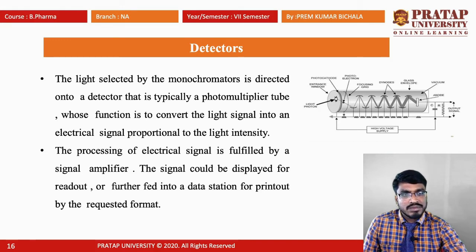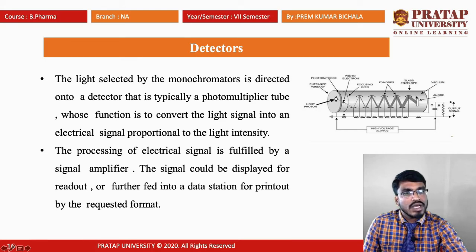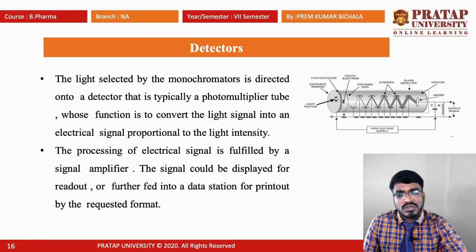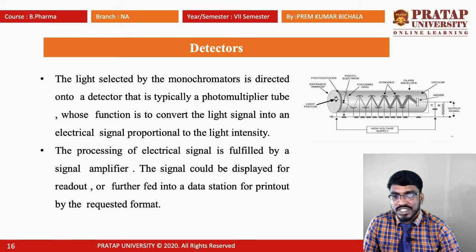In the photomultiplier tube, there are different dynodes. These dynodes catch the light from the photocathode, where the light signal is multiplied and then reaches the anode. The processing of the electrical signal is fulfilled by a signal amplifier. The signal could be displayed for readout or fed into a data station for printout in the requested format.